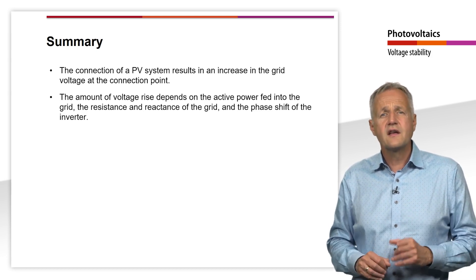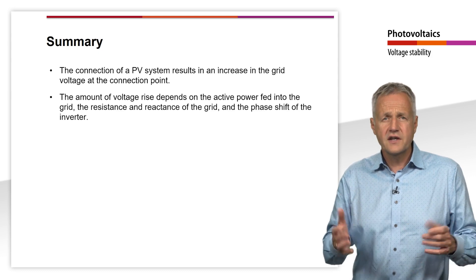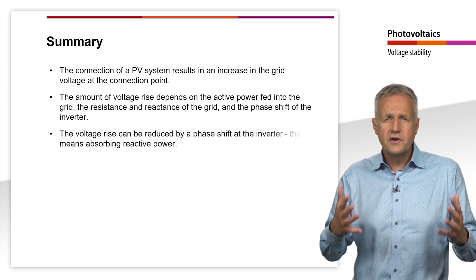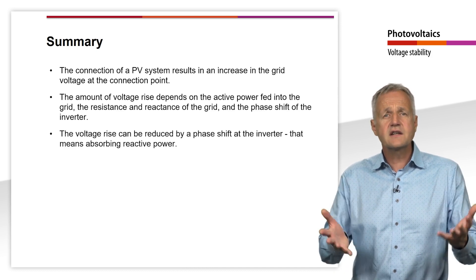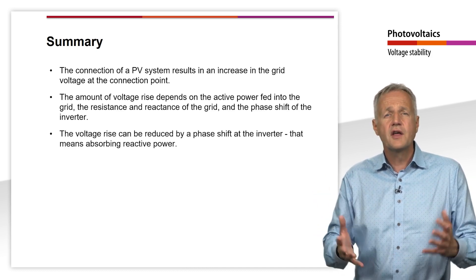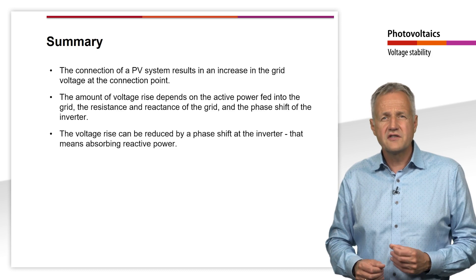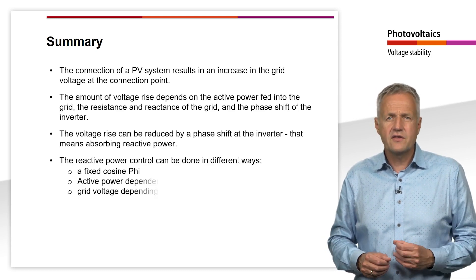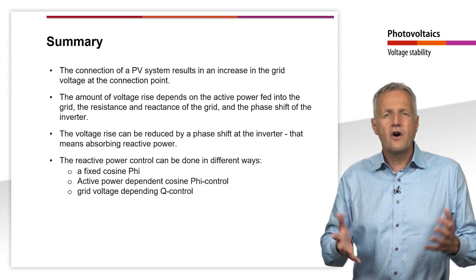The amount of voltage rise depends on the active power fed into the grid, the resistance and reactance of the grid, and the phase shift of the inverter. To reduce the voltage rise, inductive reactive power can be drawn from the grid by a phase shift at the inverter.